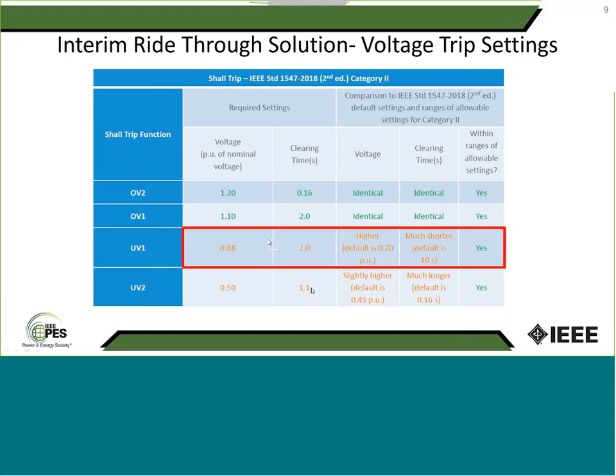And what does that mean? Based on this requirement, all generators that sense an under voltage below 50% will stop producing current, which is a good thing from a protection perspective, because they're not contributing to any faults. They immediately go to idle mode. They're not doing anything to the grid, so they don't really adversely impact the system protection. And so this was actually the key function that relieved utility distribution engineers. They said, okay, that's an acceptable function that reassures us that the distribution system protection is not going to be adversely impacted.